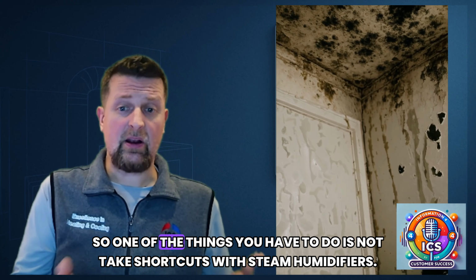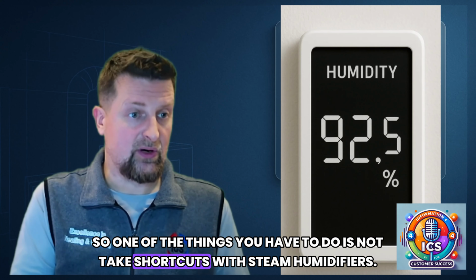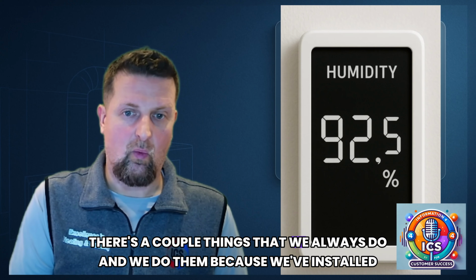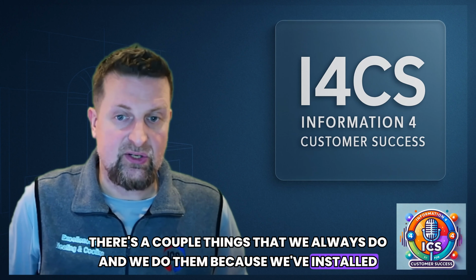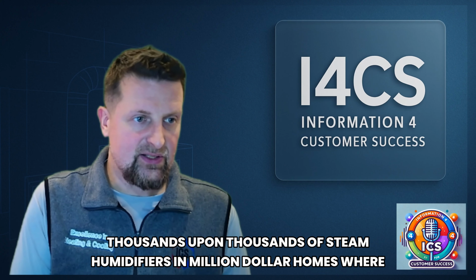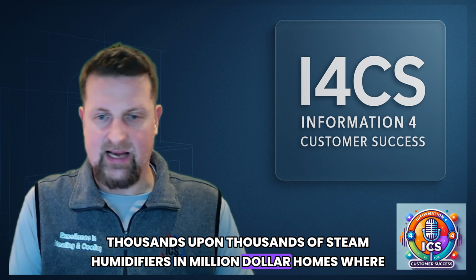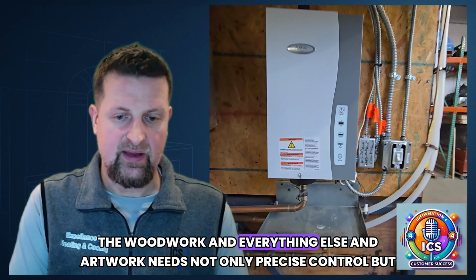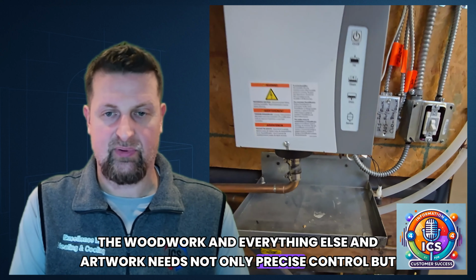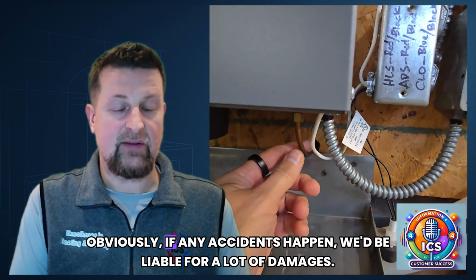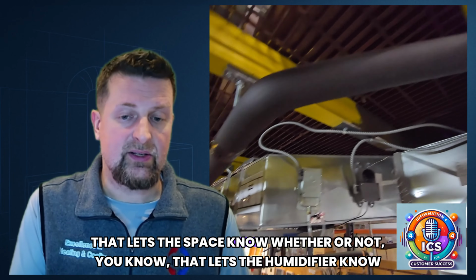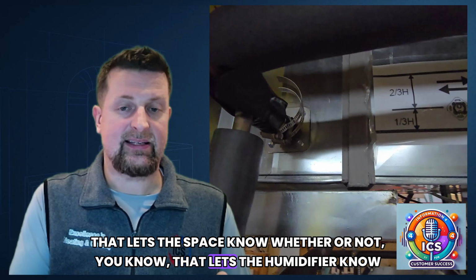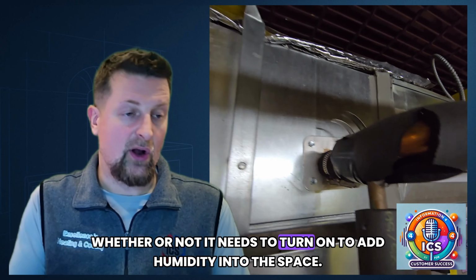So one of the things you have to do is not take shortcuts with steam humidifiers. There's a couple things that we always do, and we do them because we've installed thousands of steam humidifiers in $1-million homes where the woodwork and everything else and artwork needs not only precise control, but obviously if any accidents happen, we'd be liable for a lot of damages. So the simplest control that everybody puts in is, of course, some kind of a humidistat, whether that's on the return duct or in the space. That lets the humidifier know whether or not it needs to turn on to add humidity into the space.